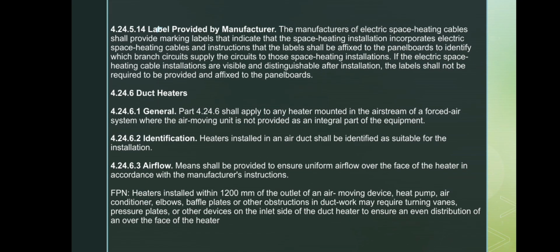Next is the marking for the heating system. Manufacturers must provide labels that indicate the installation uses electric space heating cables. These labels must be placed on the panel board to identify the branch circuits that supply the heating cables. If the cables remain visible and clearly identifiable after installation, the labels are not required.